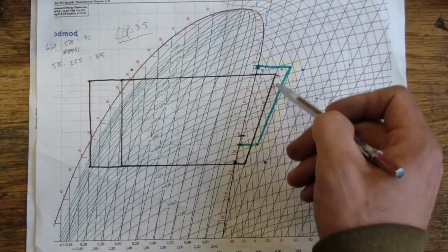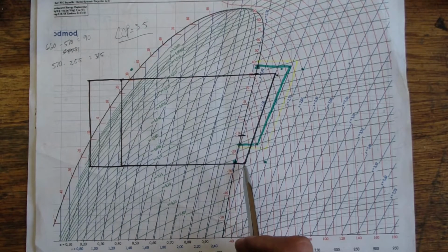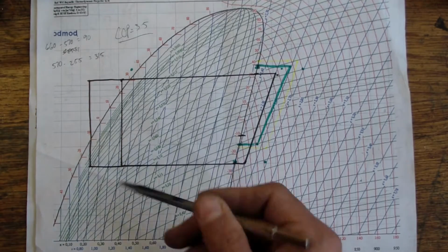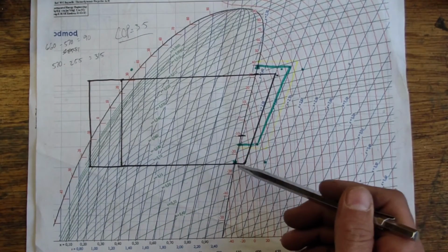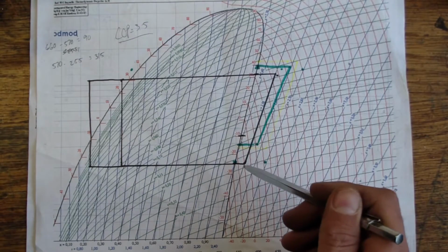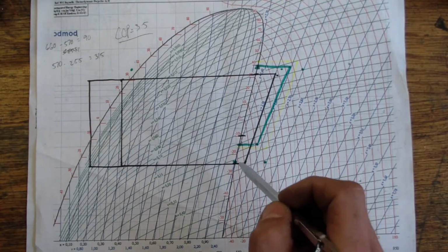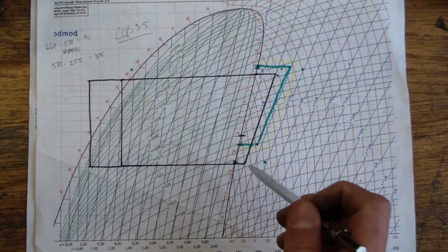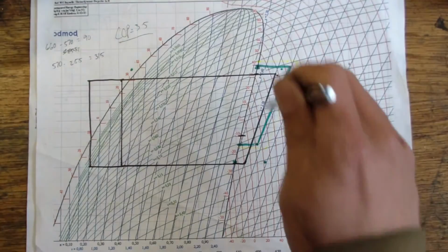So pointing out that this is the compressor right here, right before the compressor we have a saturated vapor, and then by the time it actually reaches the compressor, it's increased in temperature slightly, and it's a superheated gas existing at the suction pressure, this lower pressure here. As it leaves the saturated vapor line and enters through the suction line, and picks up some extra heat, the vapor starts to become more rarefied and increases in temperature. We can see that on the chart because we're crossing some of these isothermal lines. These are lines of constant temperature.